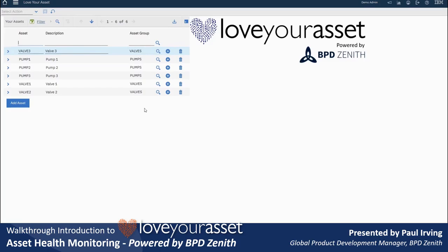Depending on the different values that have come in, we'll have upper and lower boundaries and upper and lower limits. So we'll explain what those mean. Anything within the boundaries would consider 100% health score. Anything between the boundaries and the limits will have a sliding scale of a percentage down the way, all the way to a 0% health score. And anything outside of the limits would be considered completely unhealthy, 0 health score. I'll explain this a bit further if I switch to our room example.